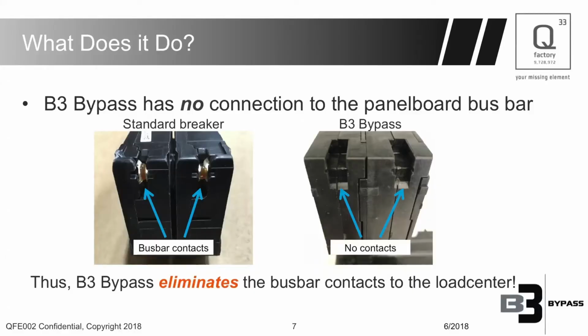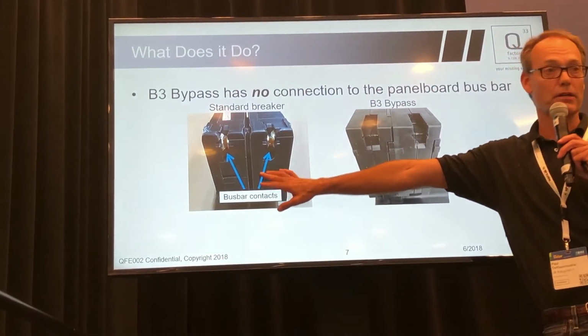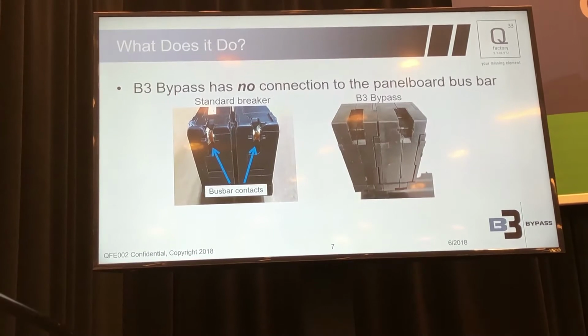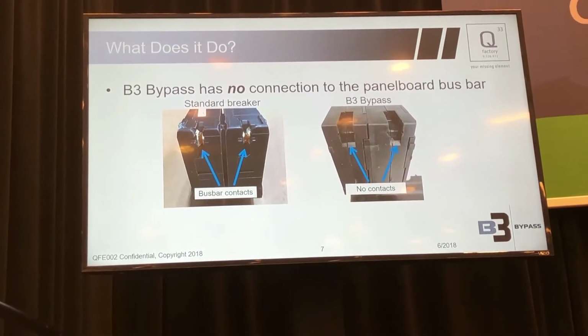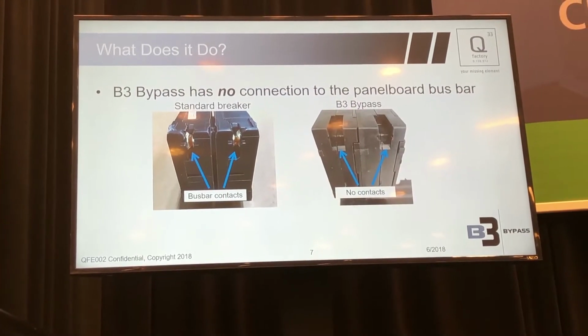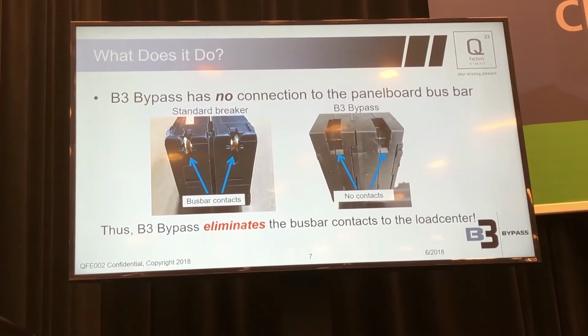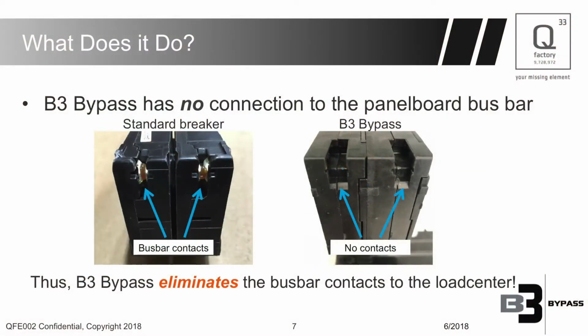What does it do? As I mentioned before, we have no connection to the bus bar of the main panel. If you look at the back of a standard breaker, this is how it looks. On the B3 ByPass, the back of it looks like this. The difference is that on the standard breaker, we have copper connection points that allow the electrical connection between the breaker and the panel. On the B3 ByPass, there's no electrical contact here. That is what's unique. This eliminates the connection, which means we have more flexibility on how much solar or how much battery we can add to that existing panel.